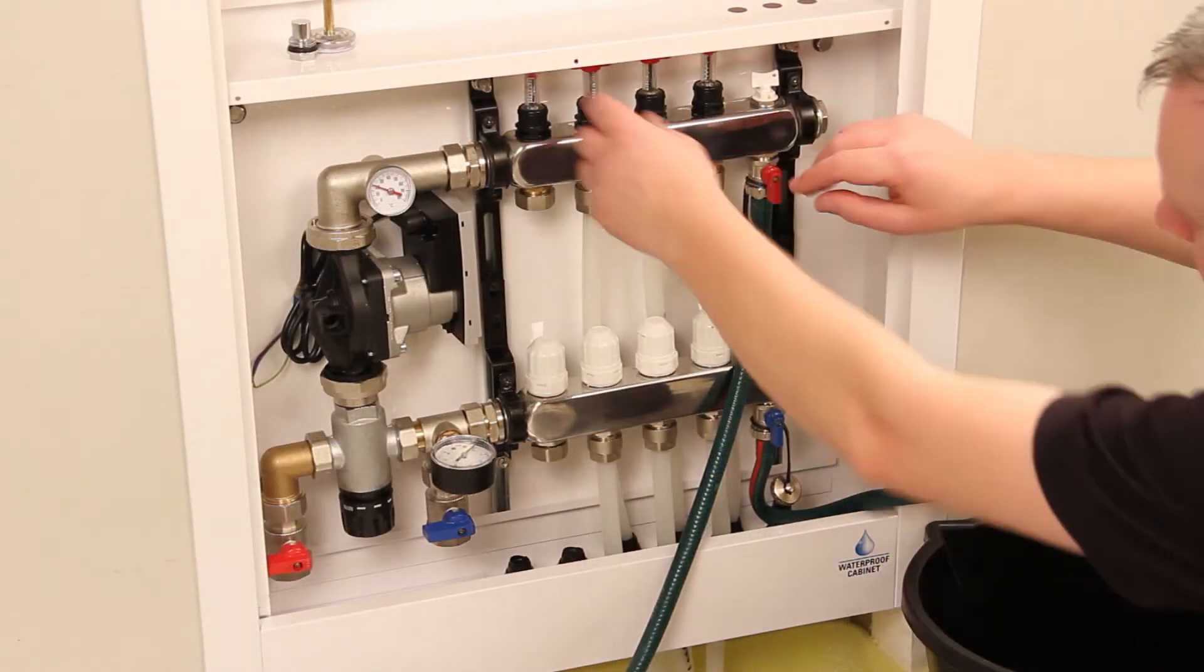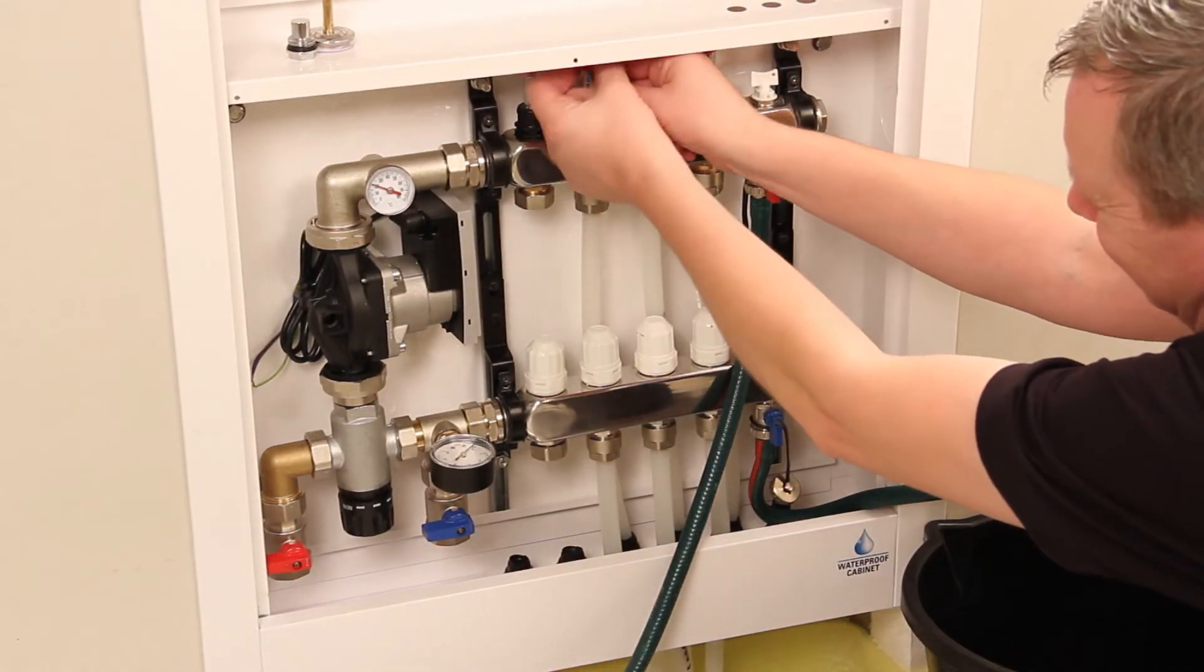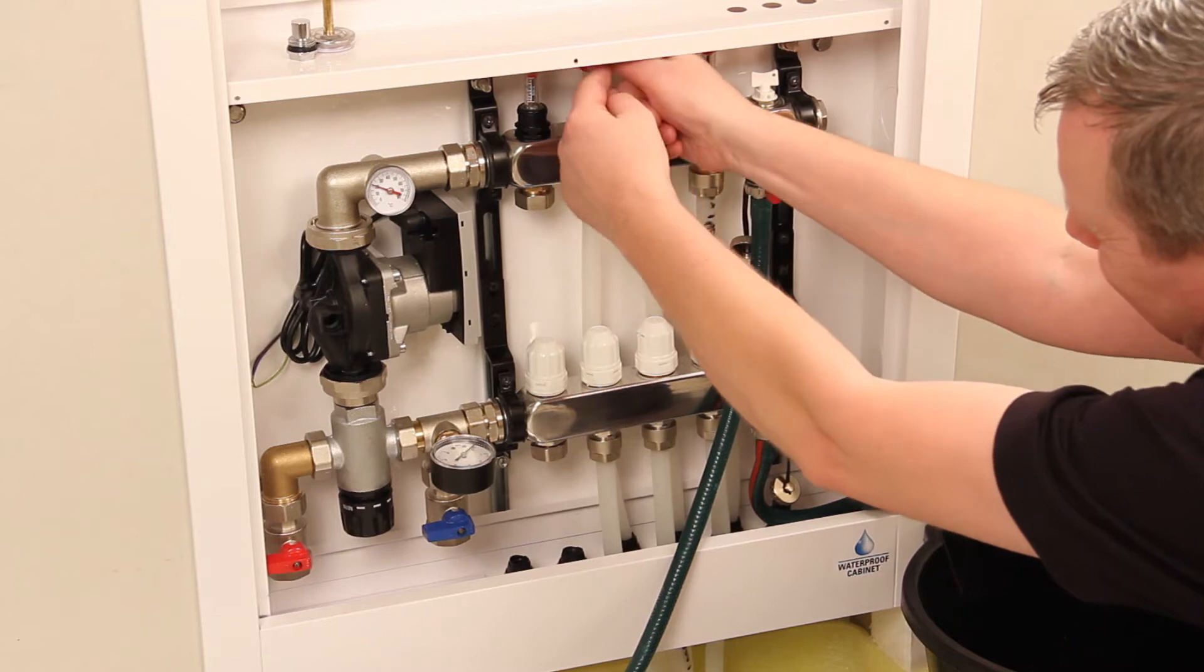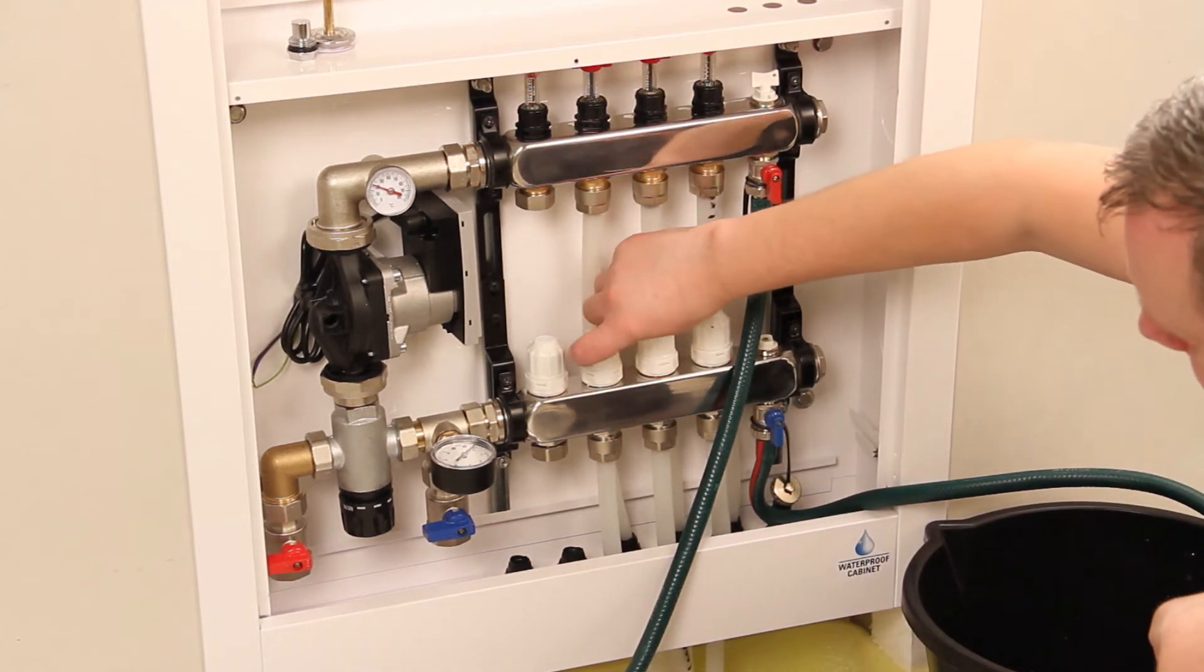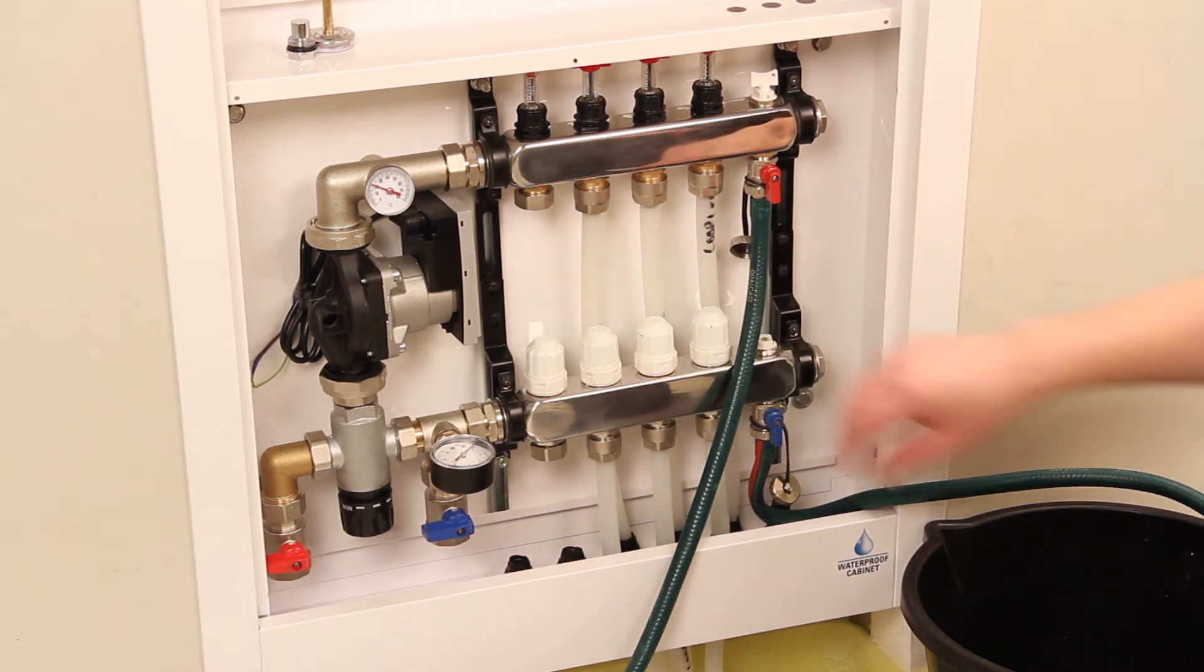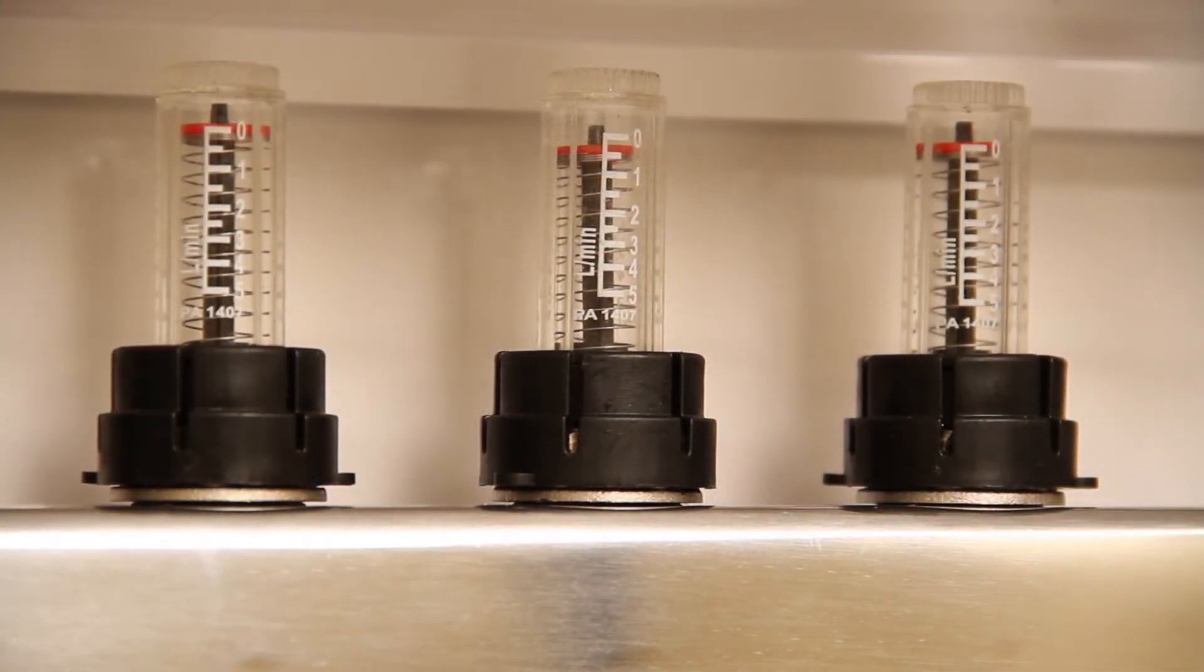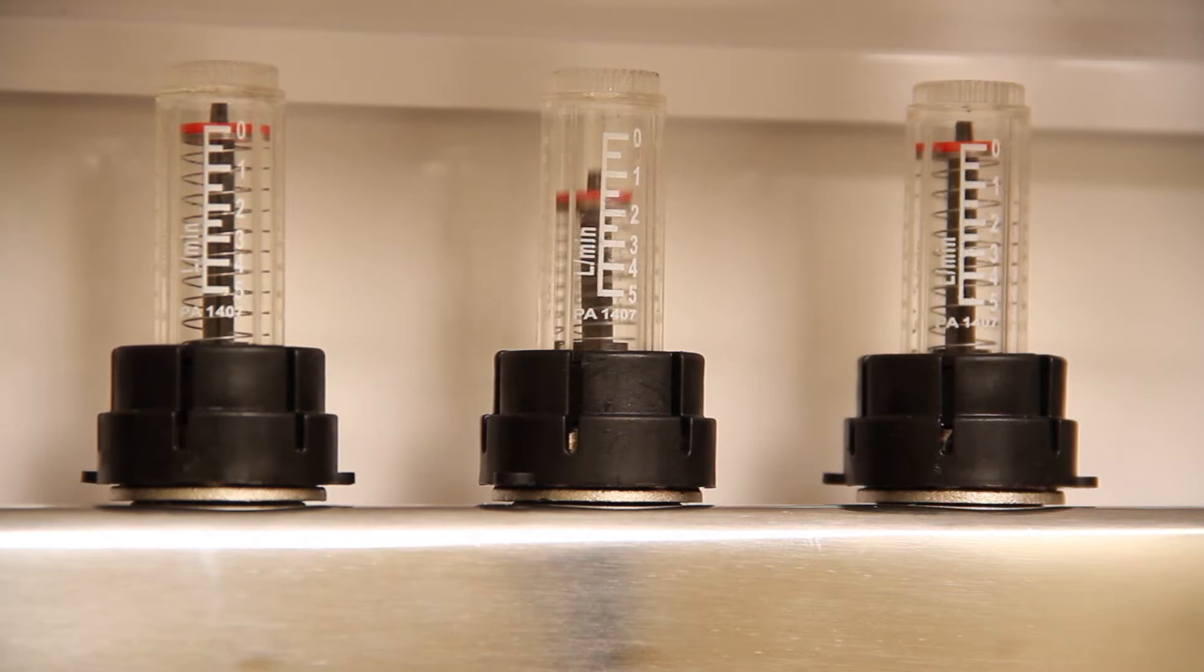Open the first flow gauge by hand a couple of turns from closed, don't force the flow gauge past the point where it becomes tight to turn. Open the corresponding manual return valve directly below the open flow gauge. Water will now start to flow through the open circuit and the flow gauge will register a flow.